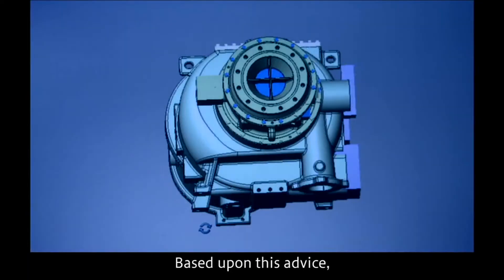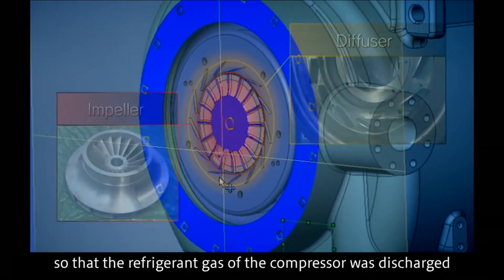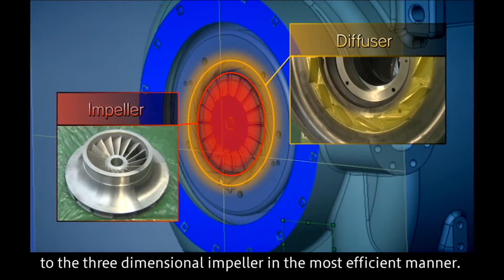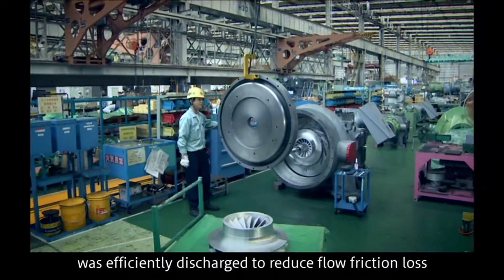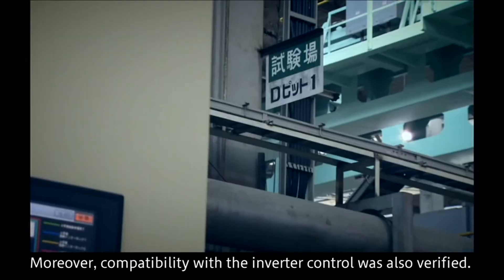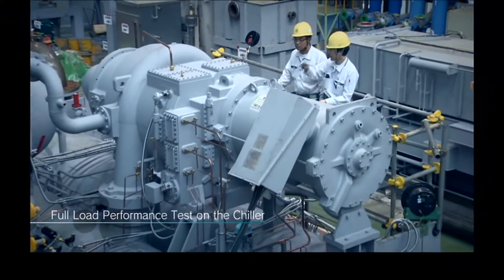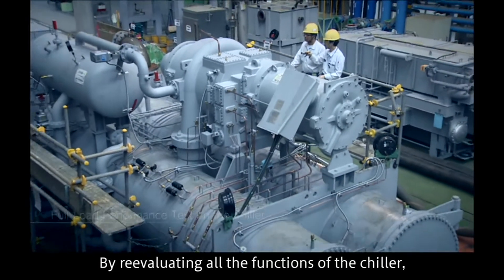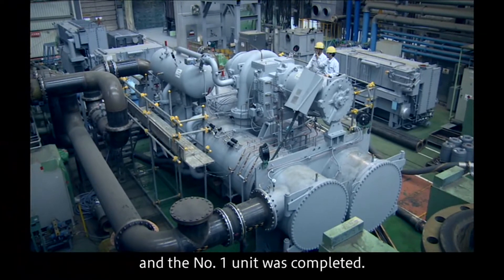Based upon this advice, the diffuser angle was calculated so that the refrigerant gas from the compressor was discharged to the three-dimensional impeller in the most efficient manner. This extensive trial and error process resulted in an ideal compressor where the refrigerant gas was efficiently discharged to reduce flow friction loss and remove air bubbles. Compatibility with inverter control was also verified. By re-evaluating all the functions of the chiller, it achieved a higher efficiency target level and the number one unit was completed.